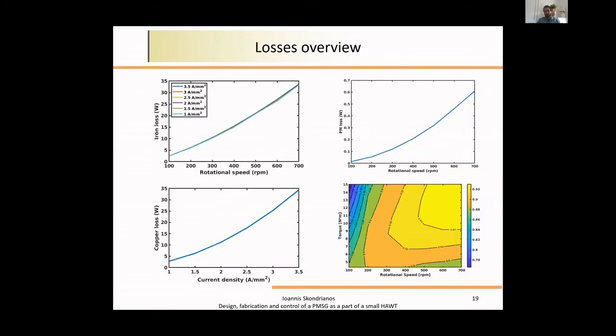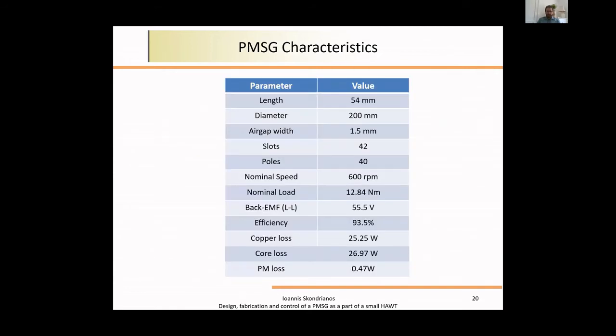This is a small overview of the losses of the machine, which we were totally expecting. As the rotational speed increases, the iron loss increases at the top left picture of the slide. As the current density increases—which depicts the load of the machine—the copper loss increases because current increases. At the bottom right picture, we can see the efficiency map of the generator, which was really good according to our supervisors. In this slide, we have an overview of the machine characteristics. The nominal torque was 12.84 Nm. The back EMF was 55.5 volts, less than the 60 volts requested by the competition. Efficiency at rated values was 93.5%.